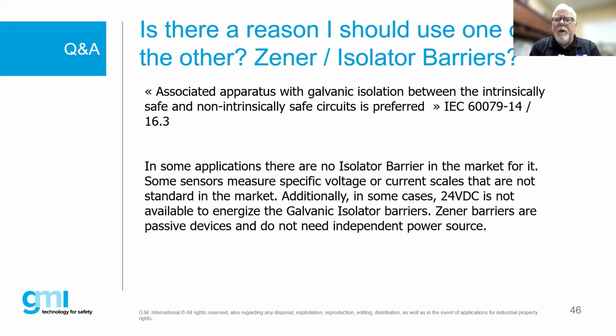The other thing to remember, true for either zener or isolator but more common for galvanic, is that you'll find them being multi-channel. Certain barriers are actually able to run either 2 or even 4 channels with a single barrier, so you might have 4 devices going through a single barrier. So when you're doing your design work, you can do some things that might save even more cost.